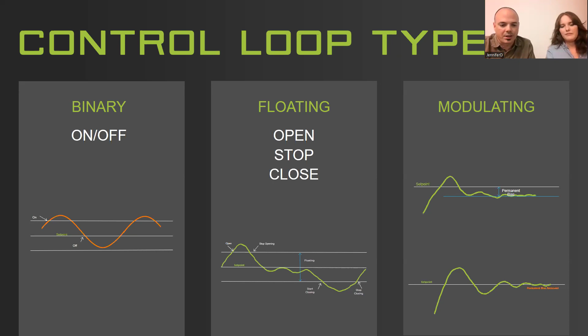You're going to usually see a pretty direct correlation. If I want that 50% valve position, I'm going to send out 5 volts DC, or 50% of that total signal range, and the valve moves to the corresponding position. That persistent value is going to basically always be moving up and down accordingly based on the output of the control loop. We could talk about this for hours, but that's the basic overview of what control loops look like and what their applications are.